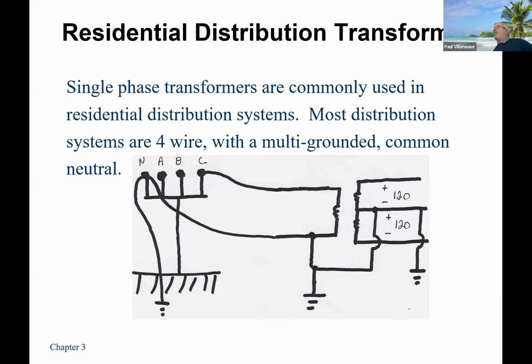So you can see this one's connected phase C to neutral. And I have a single winding that I split in the middle. This is still one winding, but I'm just pulling out of the center of those 2 and giving it my center tap. And then I take my center tap, I run that to ground, and I've got my plus 120 here, plus 120 there. It's still 240, but going across the neutral, which is what you have for your plugs, that's at the center position of the transformer. And the voltage is at 0 volts because I've connected it to ground.